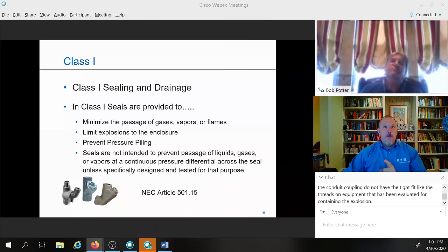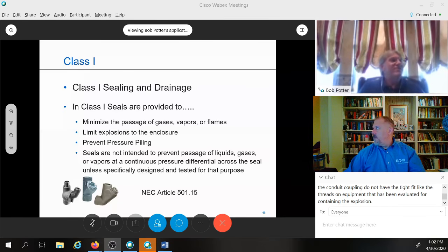explosion-proof material is automatically approved for all hazardous classified locations. And it was true, false, and not sure. We have 19 trues, 146 false, and 12 not sures. What do you say? They always say there's safety in numbers, and the 146 are correct.